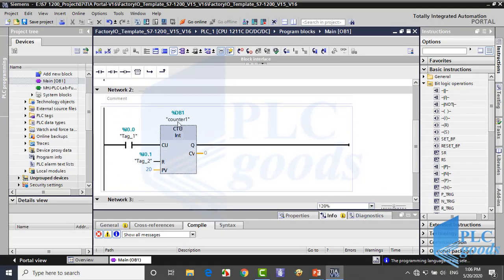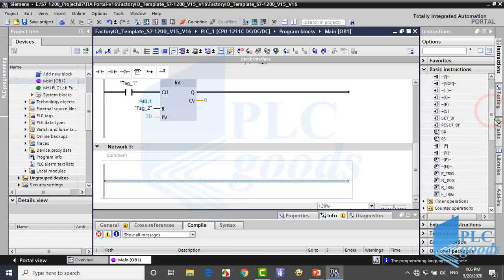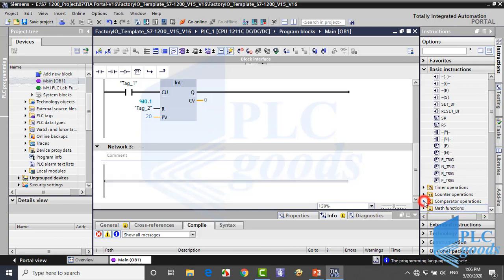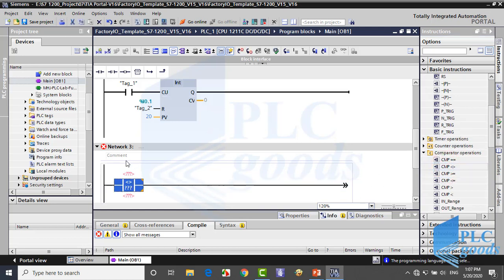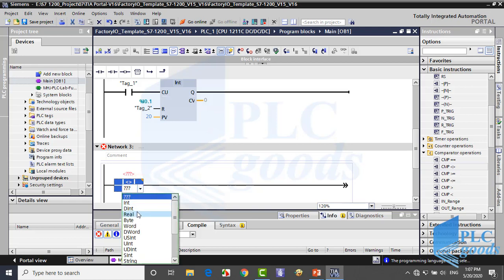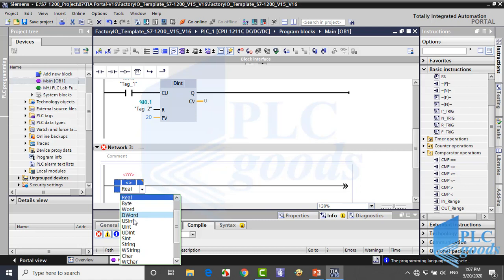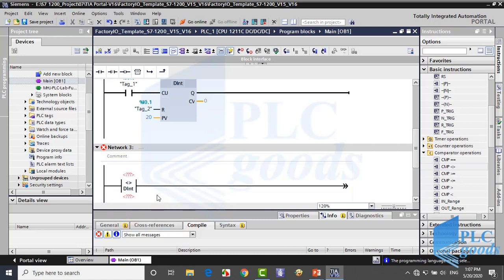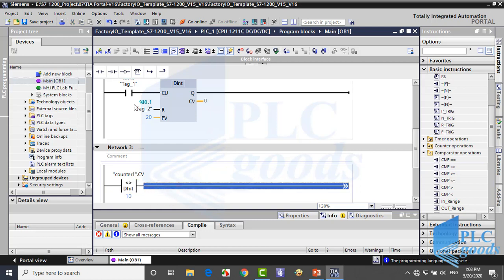Let's test some comparators. Here I've inserted an up-count counter. On the right side, click on comparator operations. I'm going to insert an inequality instruction. First I must determine which type of data are going to be compared. Let me select double integer for my counter and also for the comparator. Here I refer to the current value of the counter, and here I write 10. Now let me assign an output for this line.